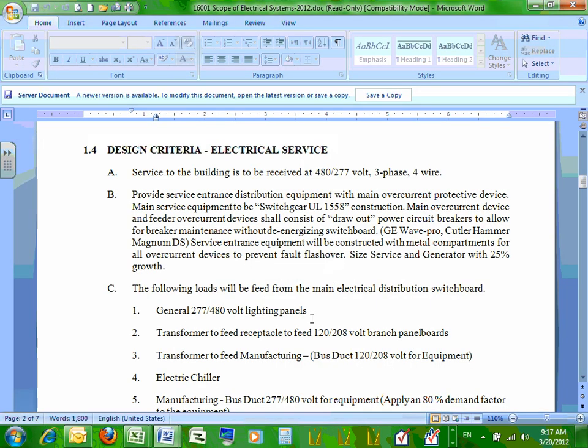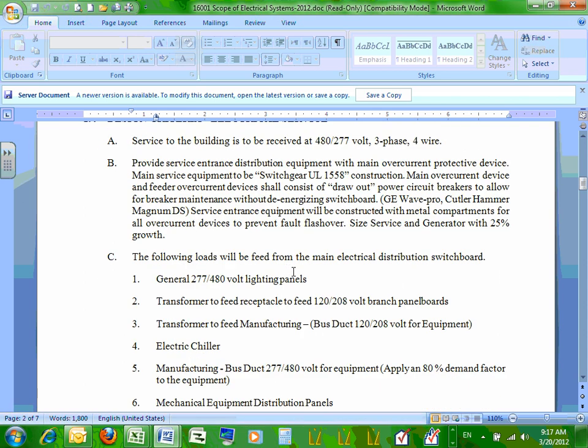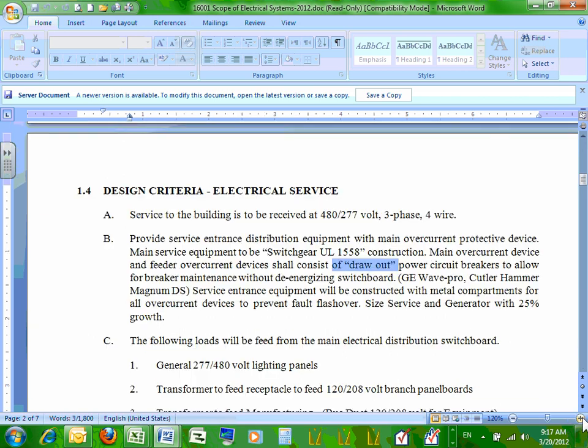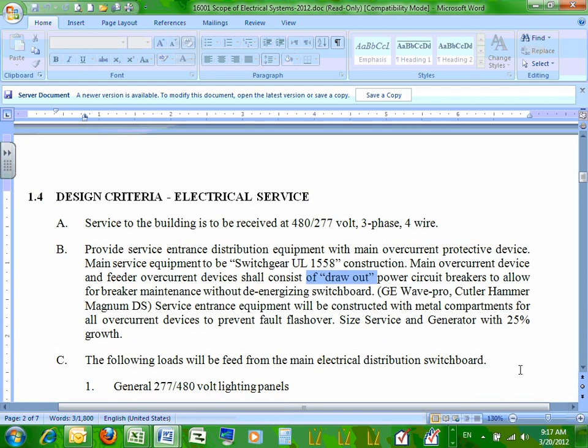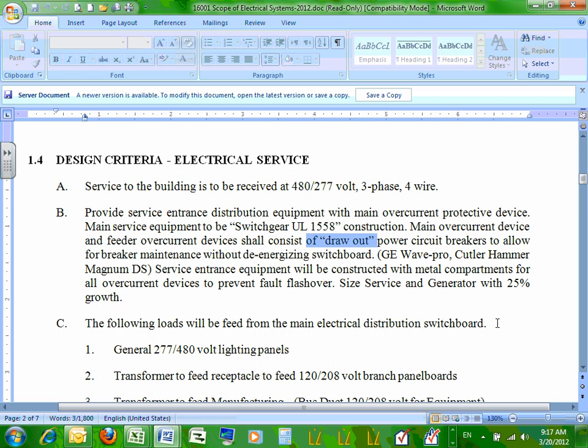I mentioned that we're making this more industrial, and so the switchgear being UL 1558 is important. It's more robust gear. It's compartmentalized, with big power system circuit breakers. You're probably familiar with the molded case breakers you might have used at the switchboard for a commercial building. This is more industrial in nature. The 1558 breakers have individual compartments for each breaker. I'm asking for the breakers to be draw out. That means you can turn this breaker off, open the door, unlatch it, and crank that breaker out for periodic bench testing and checking the tripping of that breaker. And then once it's tested and recertified, you can slide it back in and punch it back in.